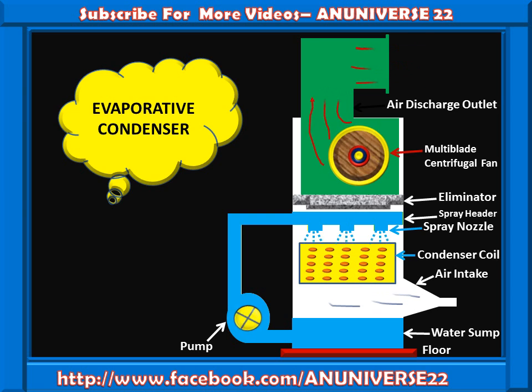Here, evaporative condenser combines the function of water cooled condenser and cooling tower, and it occupies the less space. Moreover, it needs less horsepower than a water cooled condenser.